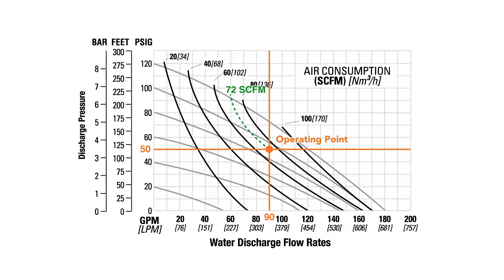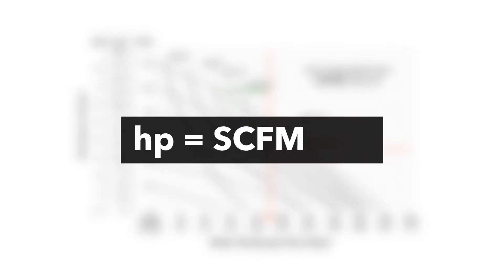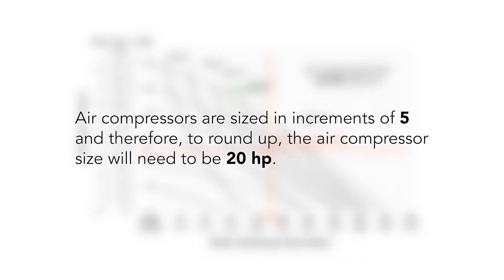To size the air compressor for your system based on the pump's 72 SCFM air consumption, use the formula: HP equals SCFM divided by 4.5. In this example, 72 divided by 4.5 equals 16. Since air compressors are sized in increments of 5, rounding up means the air compressor size will need to be 20 HP.